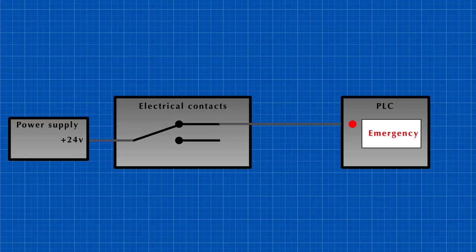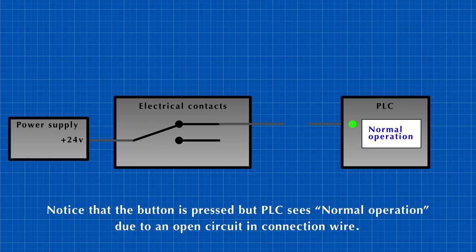Using normally open is wrong here because sometimes the button itself may not be connected properly like having a loose connection. In that case, the user will keep pressing it, but the control system will never sense it.